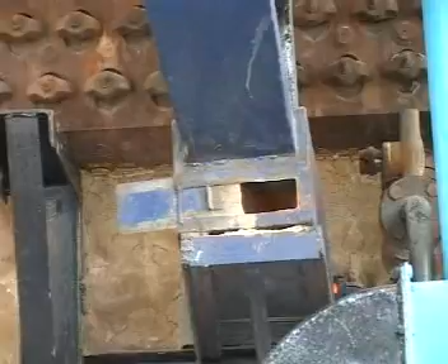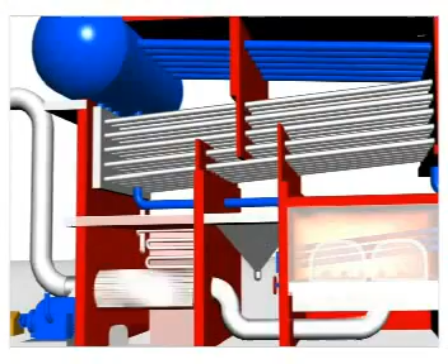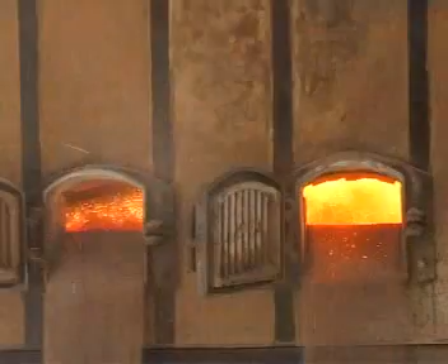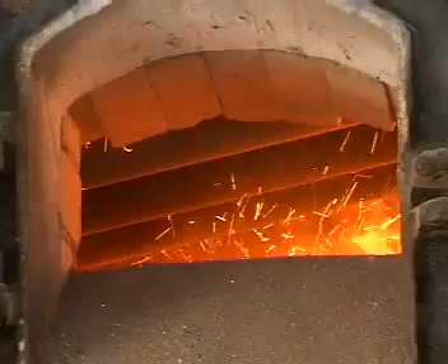Fluidization. You name the fuel, we fluidize it in our FBC furnace. Fluidizing air FD fan supplies high pressure air at around 140 to 160 degrees Celsius temperature to the FBC furnace through air preheater, and high pressure of air is converted into high velocity through air nozzles in the FBC furnace. High velocity air makes the bed highly turbulent, and it leads to the fluidization after attaining critical velocity for fluidization.